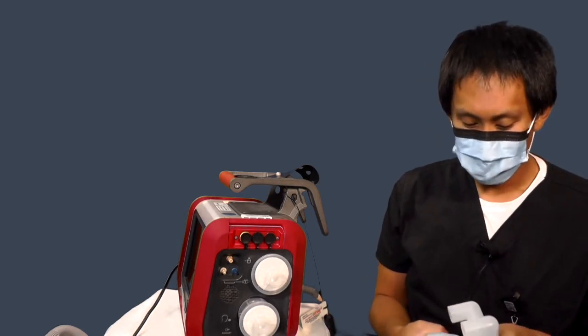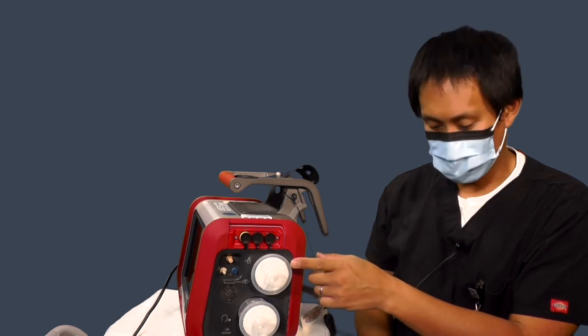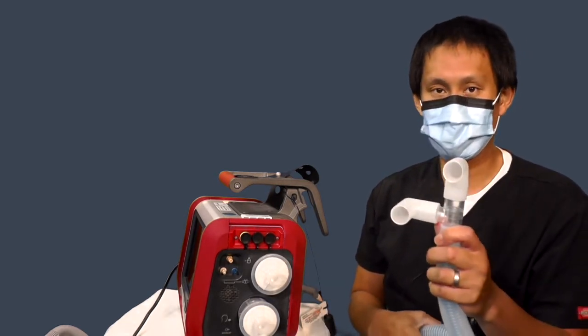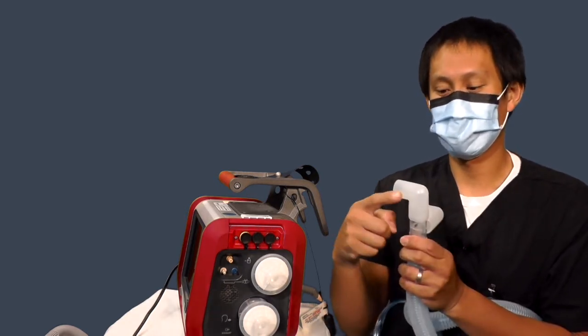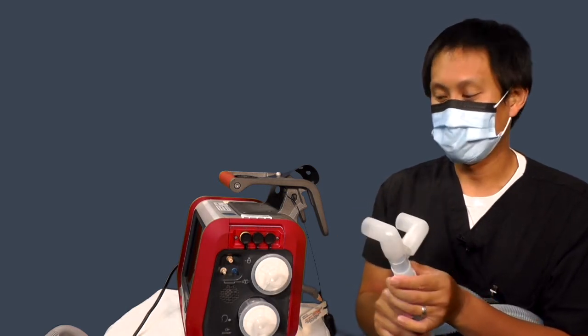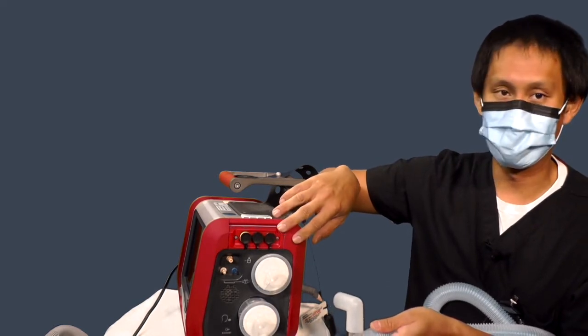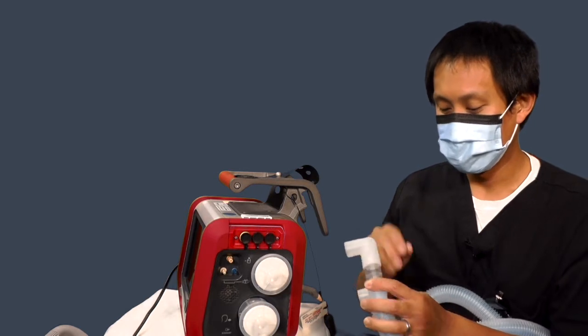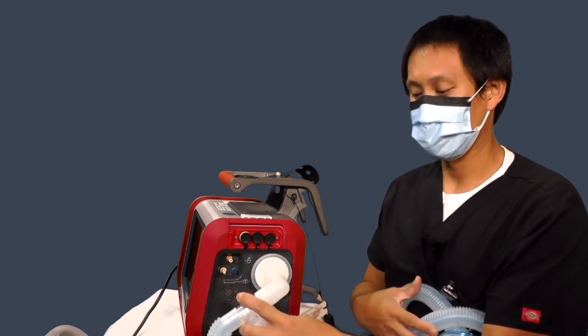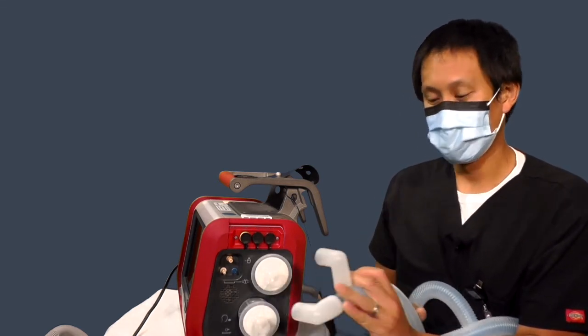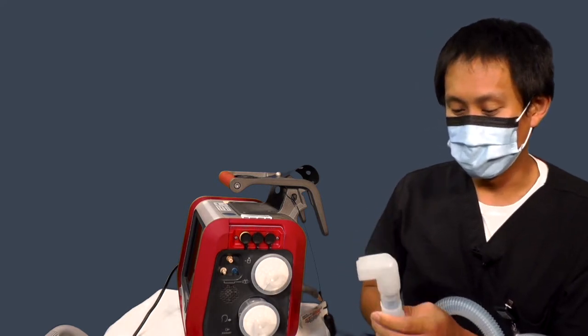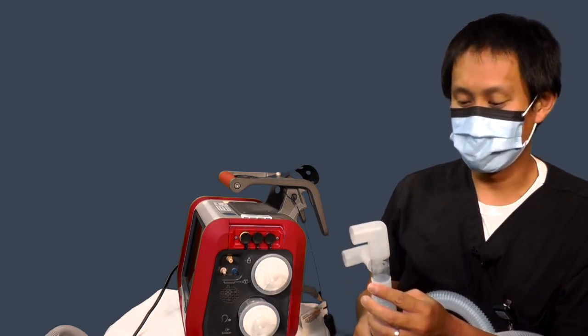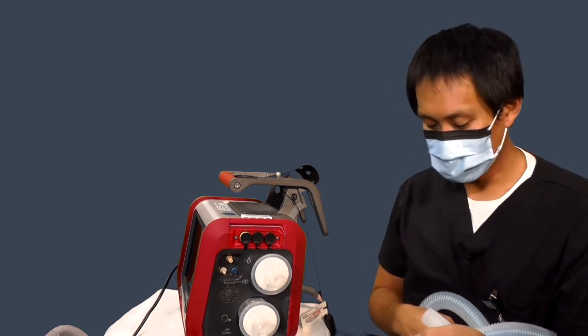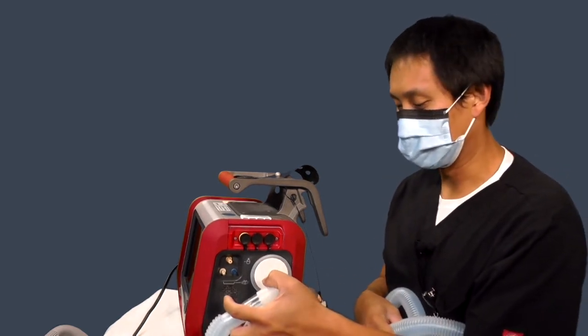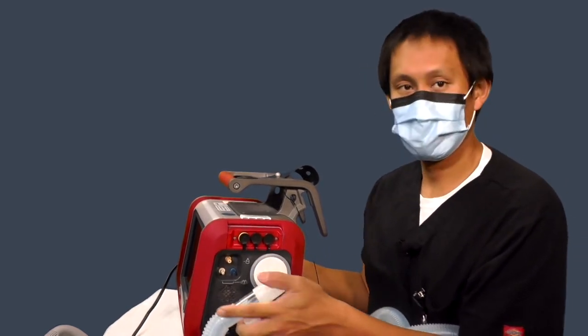As I mentioned before, the reason why you need to have two filters on the vent, or have a 6 inch extension tubing cut, is because the Hamilton circuit has a hard rigid elbow, so if you do not have another filter, it will not reach into the ventilator itself to connect. The circuit can be put on either this way or this way. There is no difference each side. It's just that the flow will be traveling through the different lumens in the circuit. Typically, we have the circuit facing towards the front of the ventilator, like so.